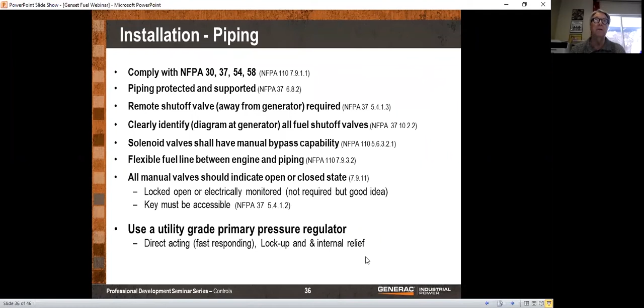You can also use propane. Propane doesn't degrade. There is no maintenance on propane. You get a propane tank and it's there for life. And so propane works very well. The natural gas, of course, you don't have to pay for the tank and you don't have to pay to fill the tank. So I'd always go natural gas if I could. But if you're in an area where you really can't get the natural gas, or if the fire marshal, for instance, says, no, you have to have on-site fuel, you can go with propane.